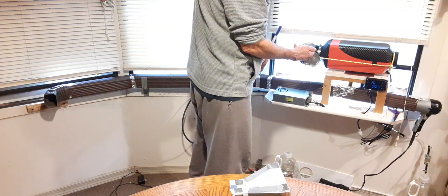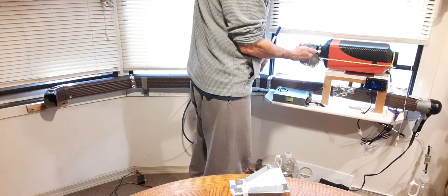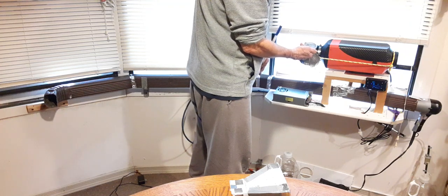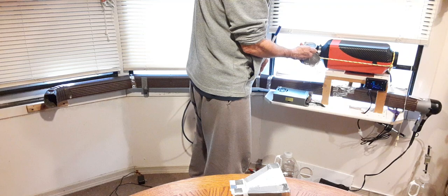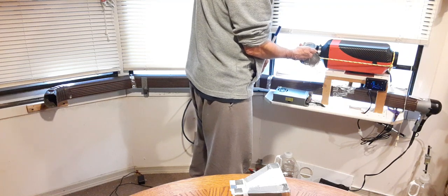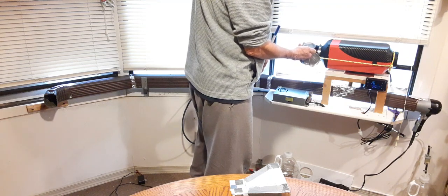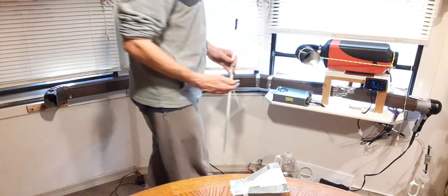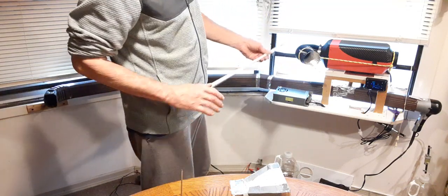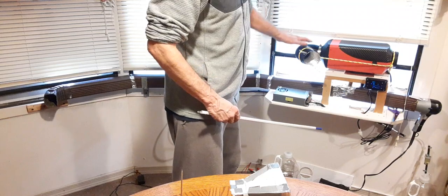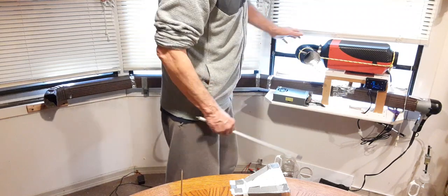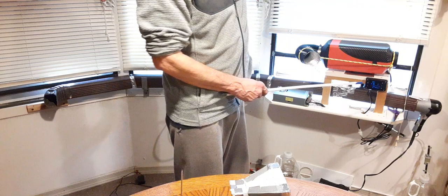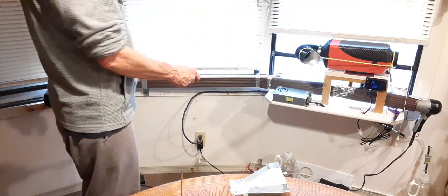I'm going to call it a stop at this point because it looks like it will go up a little higher. We might get up to 185, but it's going to take a little bit to get there, so let's call it 185. That's what I'm getting off the heater with a short runner duct with some resistance in it, and we're at level one.